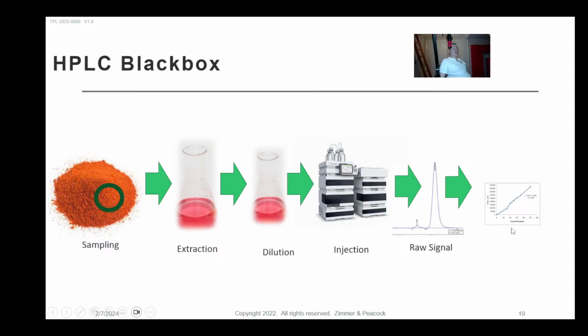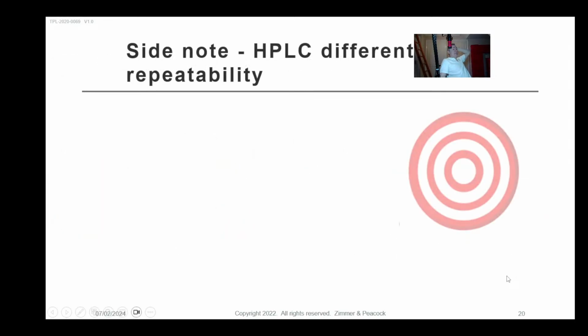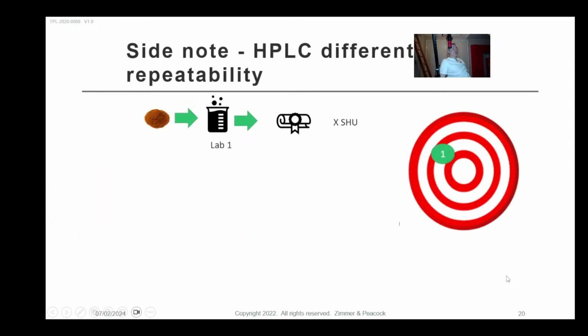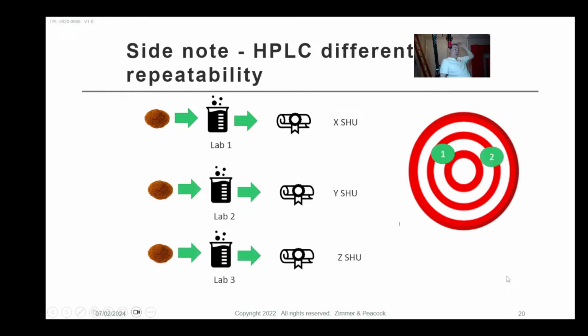But actually, they take the raw signal, they compare it against the calibration, then they give you the certificate of analysis. But you've no vision on what that raw signal really looked like, when they last did a calibration, and what that calibration looked like as well. So it's expensive to do, it's not transparent. And if you sent the same sample to different labs, I absolutely guarantee you that you will get different results.